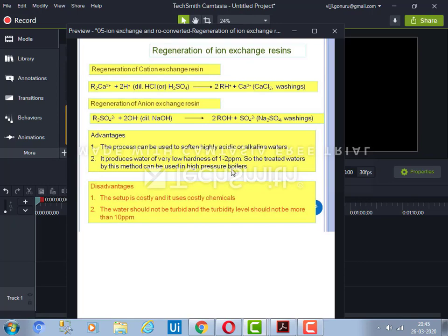Generally boilers are used for power generation. Water is boiled in the boilers, and the steam we get from the boilers is utilized for power generation. If we use salt water in the boilers, the salt will stick to the boiler container, the boiler stiffness decreases, and the boiler materials undergo corrosion. So to avoid that, we use demineralized water in the boilers.